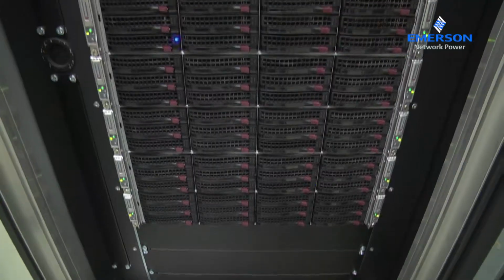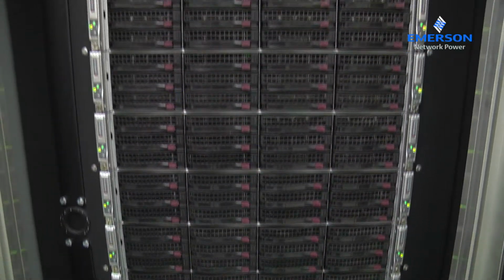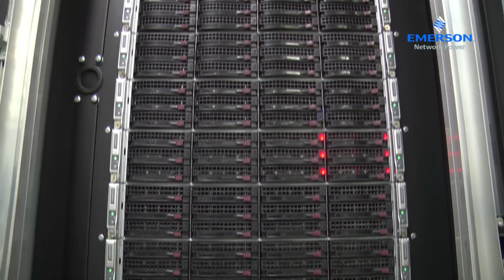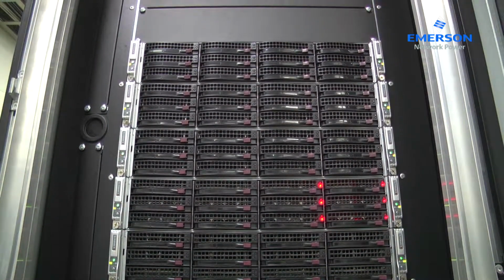Well, first of all, it is an architecture which is very simple and simply works. All the centers we have, and there are quite a few, were basically turned on and are running since without any issues. The warm air leaving the computer equipment, including ordinary computers, not only high-performance computers, is cooled back by these heat exchangers and fed back into the room. Since there's no need for cold aisle or hot aisle containment, we can mount the racks any way we want, as you see here, even in a two-story kind of housing.